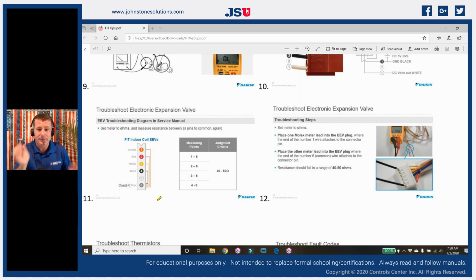and a piston that is also tapered. So as that refrigerant is flowing around that piston, it has to go through that tapered seat. And it's going to do that by how much space is in between the piston and the seat. So we can step that piston up and down simply by using some magnetic coils. That head really is that solenoid on top of that electronic expansion valve. It is just 4 coils, and each one of those will have the same resistance to each other.